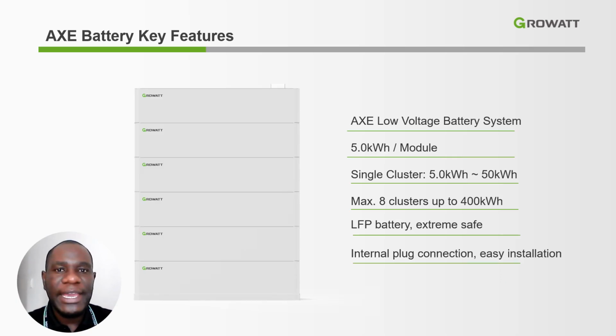Here are some of the key features of the AXE low voltage lithium battery. Each module has a capacity of 5.0 kilowatt hours, and you can scale this up in a cluster which goes up to 50 kilowatt hours, meaning that you can put 10 of them in a single cluster, and you can have a maximum of 8 clusters which goes up to 400 kilowatt hours battery capacity. This type of battery is very safe and reliable. Why? Because it is made out of lithium iron phosphate batteries, and it has got internal plug connection, hence no need for extra cabling as compared to other battery types. What does that mean? This will save the costs and also the installation time.